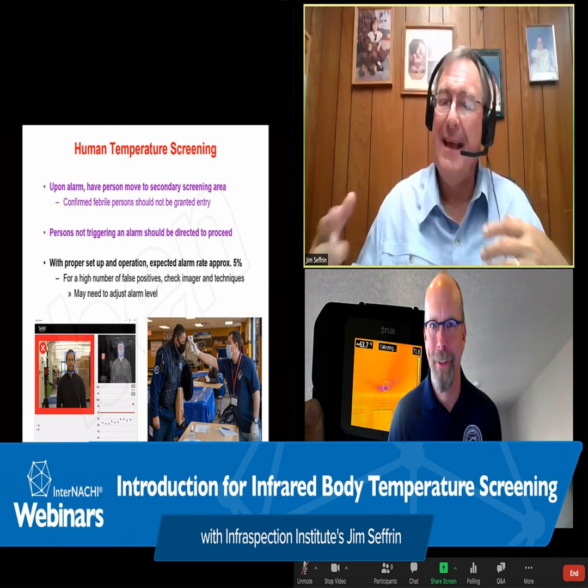I notice, Ben, behind you, or superimposed, you have a FLIR C, probably a C3. Yep. A FLIR C3, which is also an imaging radiometer. Pictured here with this slide, we see several typical modern thermal imagers. Pictured on the right-hand side are two instruments produced by FLIR Systems Incorporated. In the upper left, we have one by Infrared Cameras Incorporated, center Fotric Instruments, and down in the lower left, a Seek Thermal infrared imager.